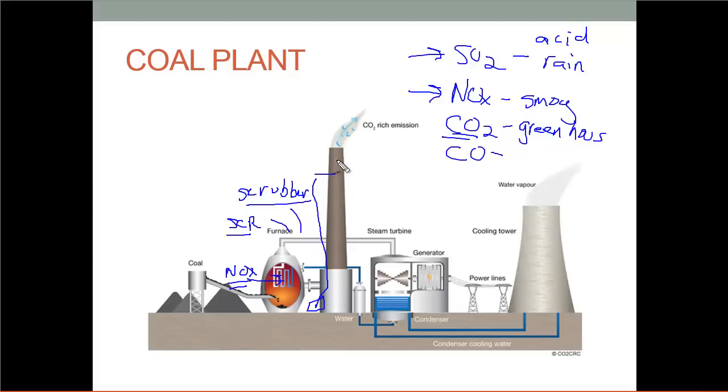So anyway, one of the things that happens is when your load profile for this plant is going up and down like this, you've got to tune the combustion process in this boiler, and you're making more, more particularly NOx than SO2, but so you're making pollutants. So it's harder to keep this thing going as cleanly as possible when the load's changing. And of course, also you've got particulate emissions and opacity issues because nobody wants to see a bunch of smoke coming out of the stack. So tuning this boiler when it's following load like this becomes a little bit of an issue, and it's an operational problem for the power plant operator.